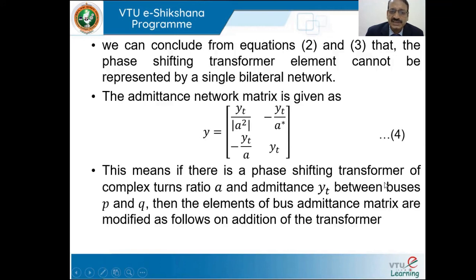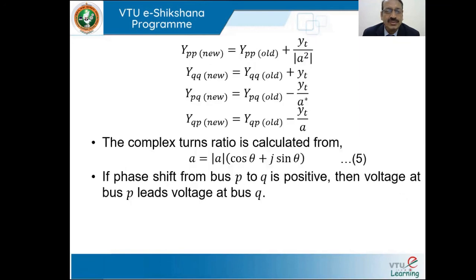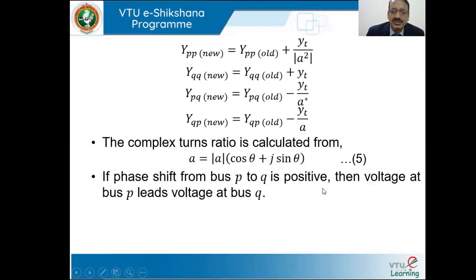Since IPQ and IQP are not equal, the phase shifting transformer cannot be represented by a single bilateral network. The admittance matrix element Y for the transformer is: Y11 = YT/A², Y12 = −YT/A*, Y21 = −YT/A, Y22 = YT. For a phase shifting transformer of complex turns ratio A and admittance YT between buses P and Q, the bus admittance matrix elements are updated as: YPP_new = YPP_old + YT/A², YQQ_new = YQQ_old + YT, YPQ_new = YPQ_old − YT/A*, YQP_new = YQP_old − YT/A. If the phase shift from bus P to Q is positive, the voltage at bus P leads the voltage at bus Q.